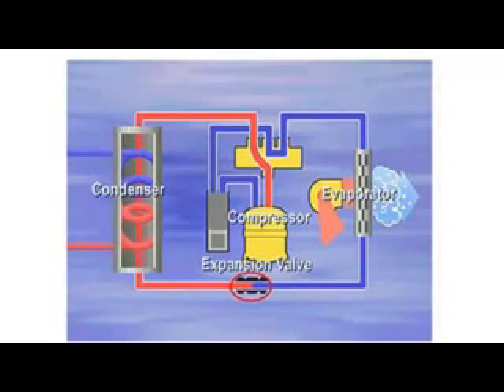The refrigerant moves into the compressor, which is a pump that raises the pressure so it will move through the system. The increased pressure from the compressor causes the refrigerant to heat to roughly 120 to 140 degrees. The hot vapor now moves into the condenser, the underground loops, where the refrigerant gives up its heat to the cooler ground and condenses back into a liquid. As the refrigerant leaves the condenser, it's still under high pressure. It reaches the expansion valve, where the pressure is reduced. The cycle is complete as the cool, liquid refrigerant re-enters the evaporator to pick up room heat.